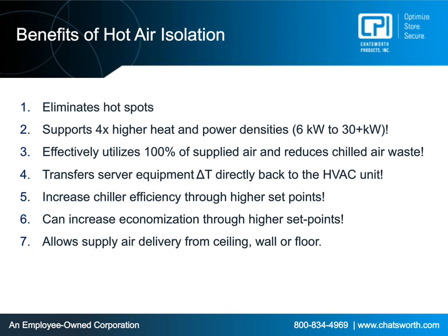Then once you get to 5, now you're starting to have some real fun in your data center. You can increase your set points. So you do not have to run your data center at 59 degrees or 65 degrees. You can now run it in the 70s, even all the way to 80. ASHRAE has a spec out that 80.6 is the hottest it could be in your cold aisle. That's pretty hot. So we're going to try to get those set points up.